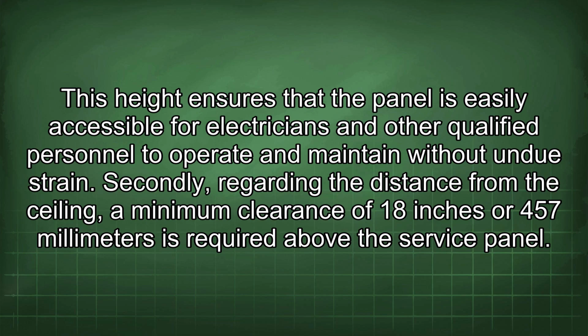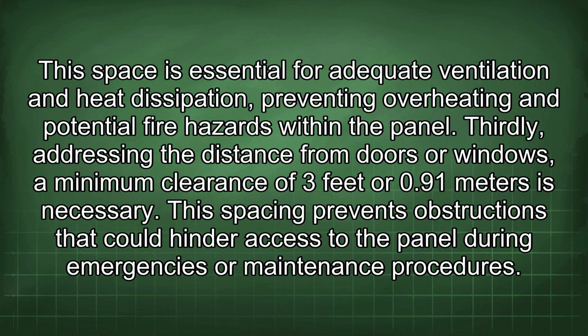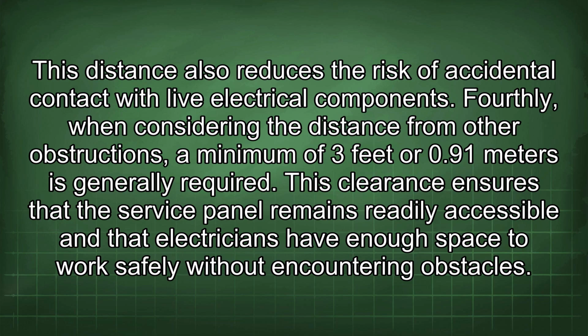Secondly, regarding the distance from the ceiling, a minimum clearance of 18 inches or 457 millimeters is required above the service panel. This space is essential for adequate ventilation and heat dissipation, preventing overheating and potential fire hazards within the panel. Thirdly, addressing the distance from doors or windows, a minimum clearance of 3 feet or 0.91 meters is necessary. This spacing prevents obstructions that could hinder access to the panel during emergencies or maintenance procedures. This distance also reduces the risk of accidental contact with live electrical components.